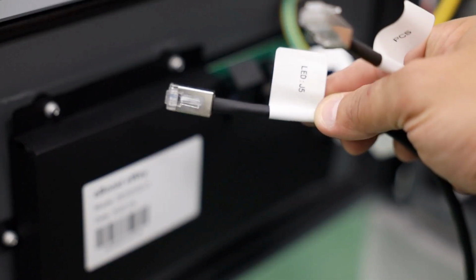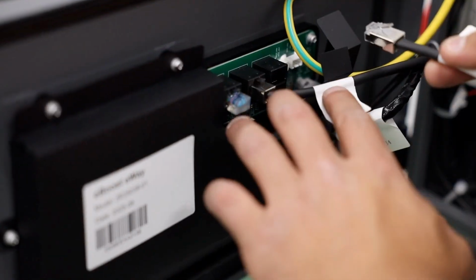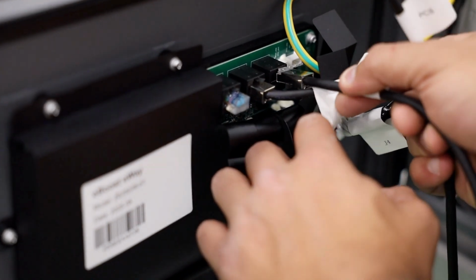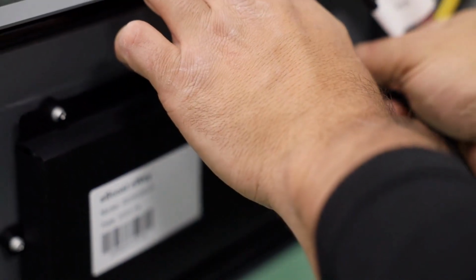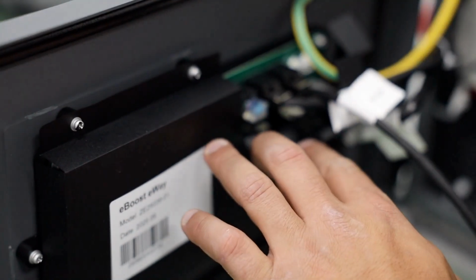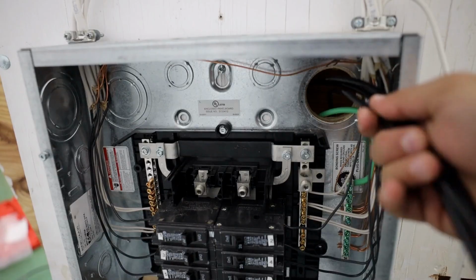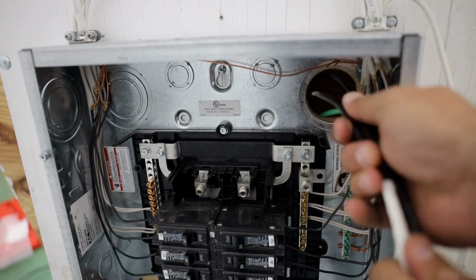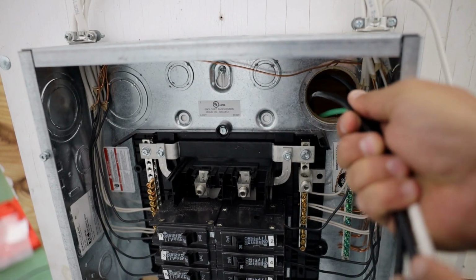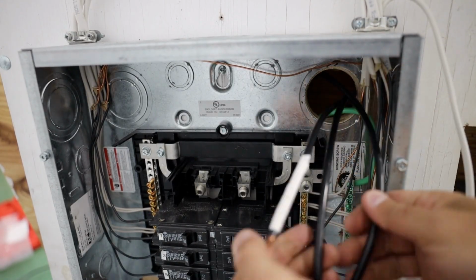Use the battery to inverter communication cables, RJ45 cable, and connect one end on the battery and the other end at the inverter bat communication port. Make sure to use the cable included with the battery packaging to guarantee correct closed-loop communication. Reminder to always make sure to adhere to local AHJ regulations.